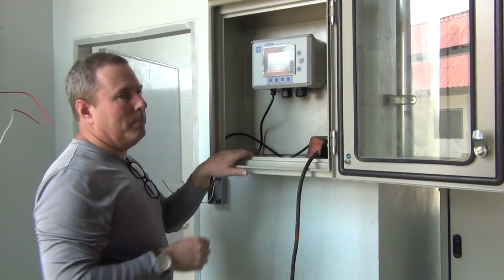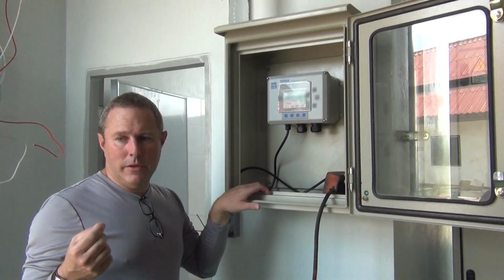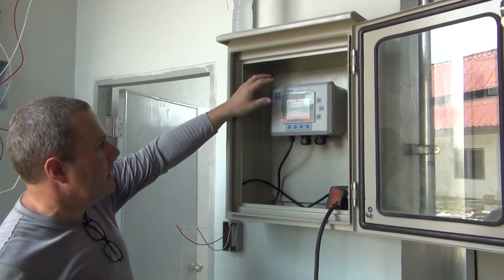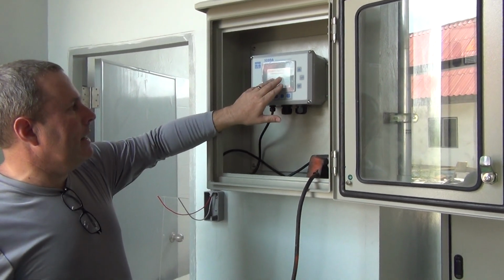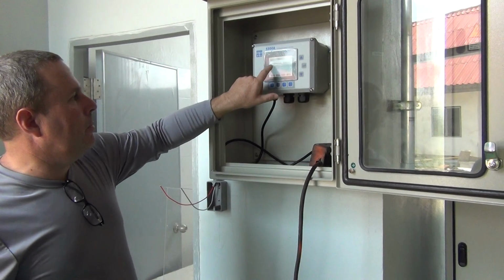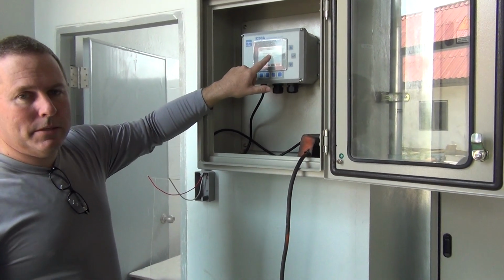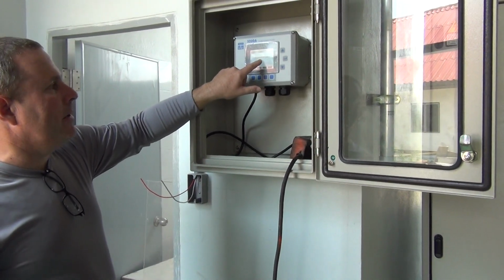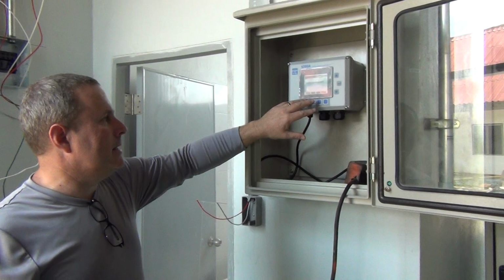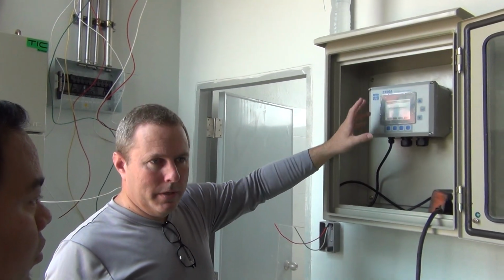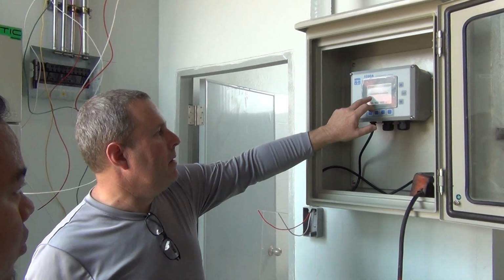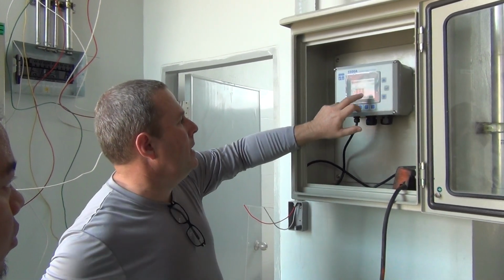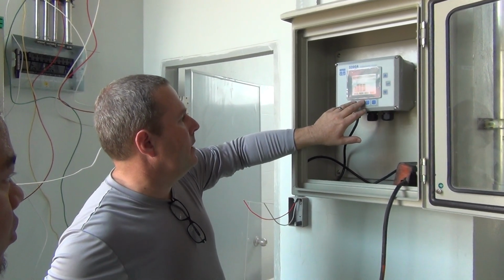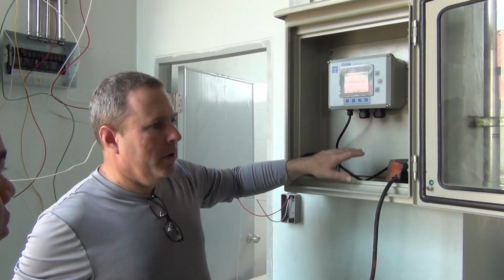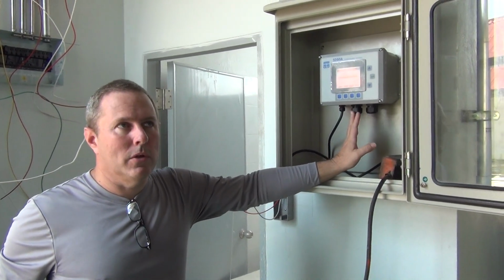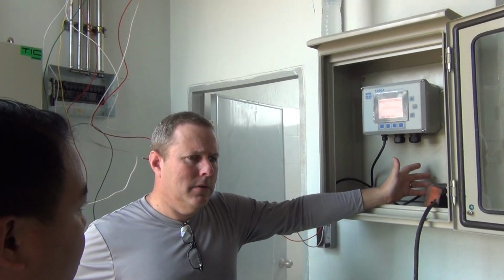So then, power fail. Do you want to be notified if there is a power failure? So we can go to power fail, and the power failure system can be enabled or disabled. We can also monitor the AC supply, and if you were using a battery, you can set it so that if the battery goes low, it would send an alarm. And then you can have a low battery trigger, which would be what voltage you want the battery to take over. So you can have AC power of 85 to 264 volts. If your nominal power is what, 230, 220?